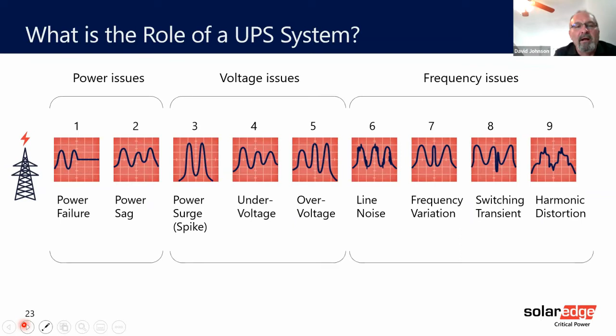Rectifier serves to convert AC to DC, so that you have a DC bus connected to the battery, which then feeds the inverter when we're on battery, when the power's gone. The inverter inverts from DC to AC, giving you a clean 100% recreated sine wave on the output. So if you have poor power on the input, through this conversion process, we're going to give you power quality on the output. And then the bypass is for emergencies, if there's a problem, or to do maintenance.